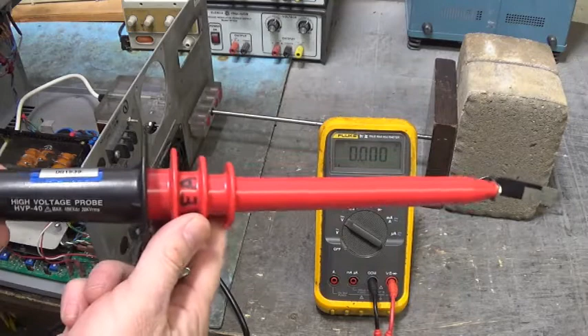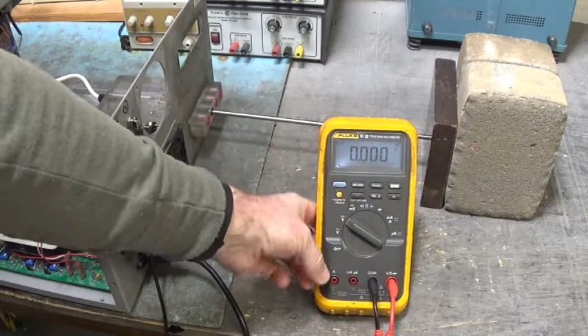Grab my meter, see if I can put it someplace where y'all can see it. Y'all see that right there? Turn that to volts. Now here's the high voltage probe. It has probes for your meter, and it has a clip for frame ground. All that comes out of the back of the high voltage probe. So we clip the high voltage probe to frame ground. Let's turn this on so we can see. This probe is rated for 40 kilovolts DC and 28 kilovolts RMS, root mean square.